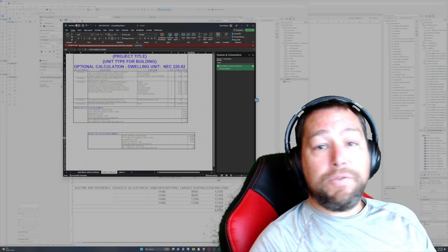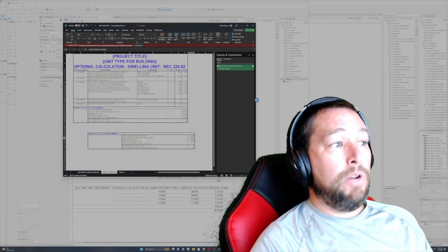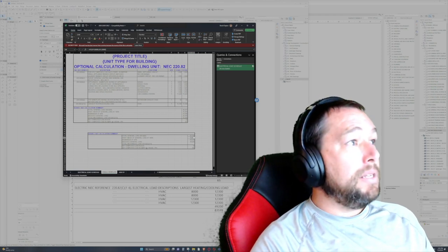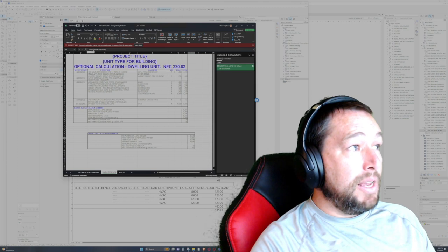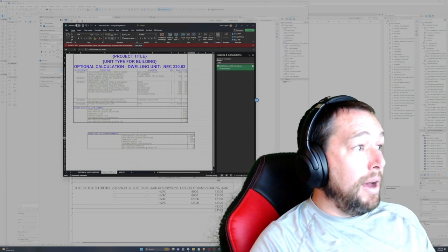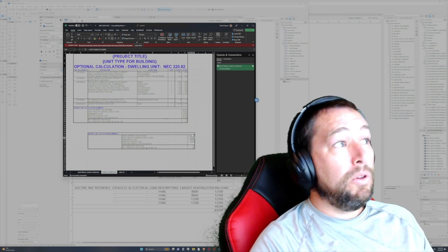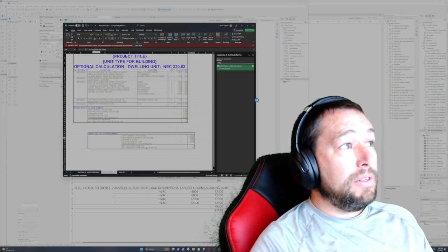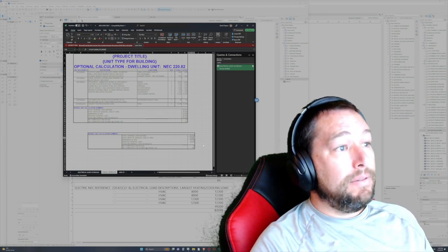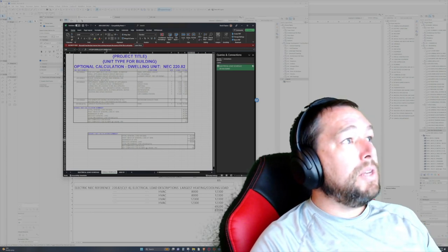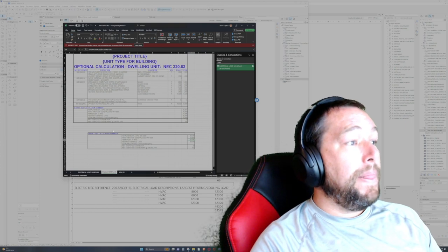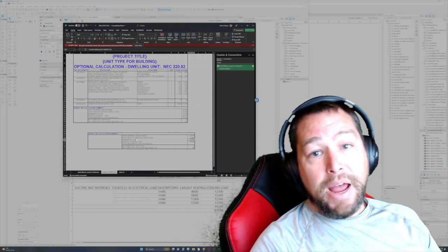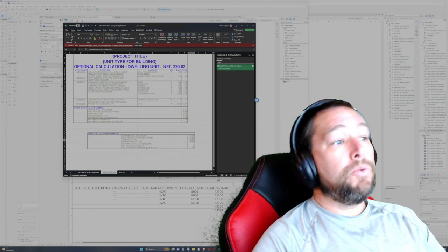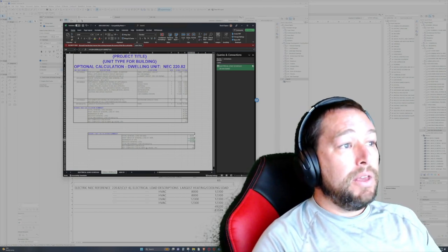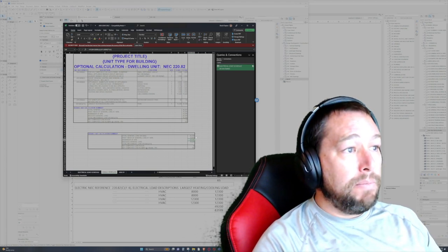Then this next cell calculates the first 10 kilovolt-amperes of general load at 100%. That takes an if statement on I37, our general load total — if less than 10,000, then continue, if not, then continue. The next one is a similar if statement that takes the remainder at 40%, so that's your load reduction. The first 10,000 of the 83,599 is going to be 100%.